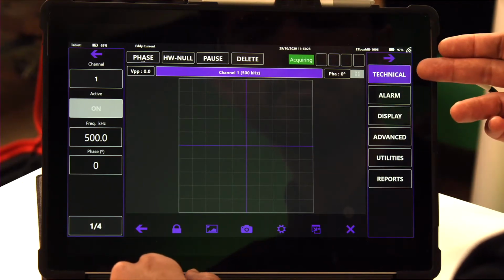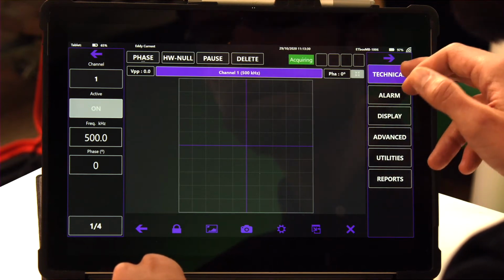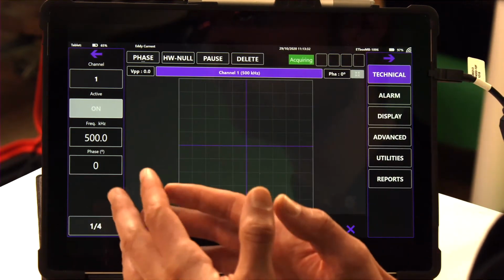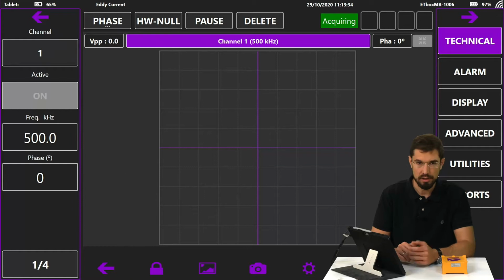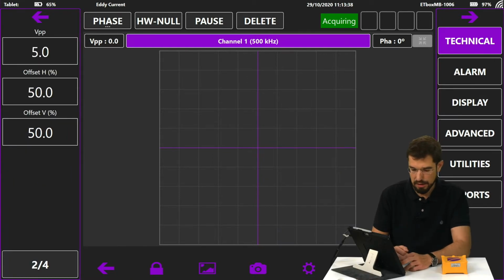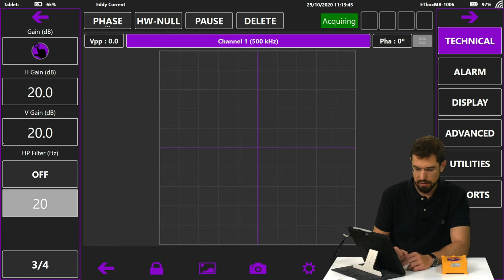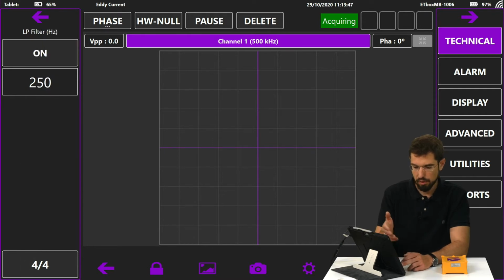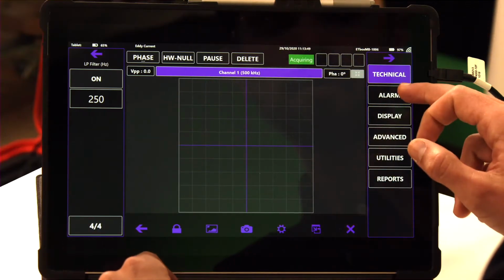The first one, the technical one, grants access to set up all the eddy current parameters you can need, such as the gain, the attenuation to the probe feed, or the offset of the signal you're working with. Here we have gain, or even the control of the filters.